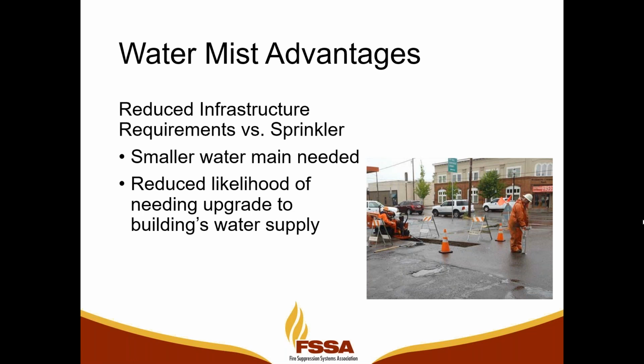Just as an example, we've had fast food restaurants periodically say every 10 years they'll do a gut and rehab of their facilities to modernize them. Well, we've had instances where a restaurant's undergoing that process, and the local authority and the building owner look at the current water supply, they look at what's gone on in the neighborhood in the intervening 10 years, and they see that the infrastructure, the buildings around that restaurant have built up over time to the point that the feeder line from the main to that building is no longer adequate for that building's sprinkler system. So they're faced with trenching across parking lots and sidewalks and laying a larger diameter supply line.